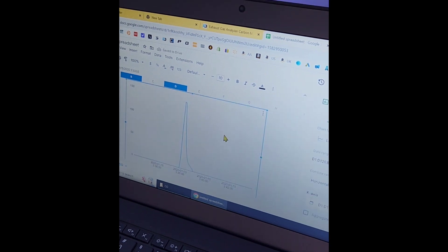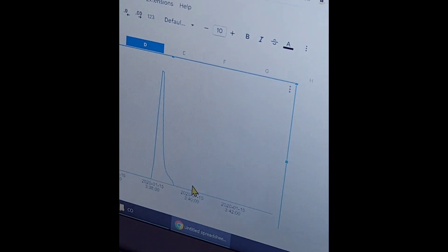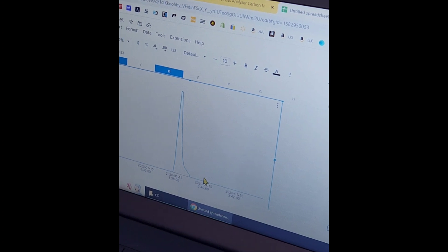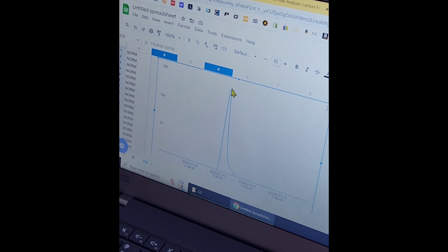I've imported the data from the drive into Google Sheets and now all I need to do is simply graph it — quite straightforward. And there we see the spike from when we exposed the analyzer to the gas. Our carbon monoxide spiked and reached, as we can see from the graph, just under 150 within a few seconds.